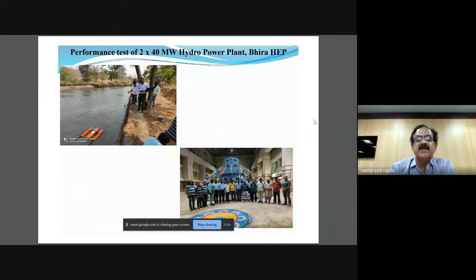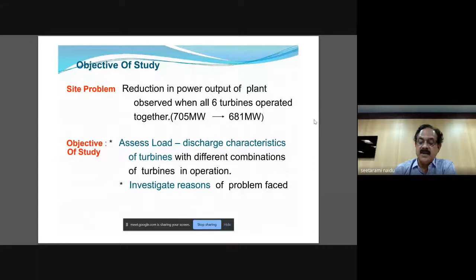The problem observed was a reduction in power output of the plant when all 6 turbines operated together. 705 megawatt was the required plant capacity, but there was a miss of 25 megawatt, only 685 was possible. So an investigation was done, I think sometime in 1995 or so, and we recommended replacement of the turbine with changed specifications. They implemented it, and now tested again 2 years back, in 2017, it is generating 10% more. This was the earlier studies.